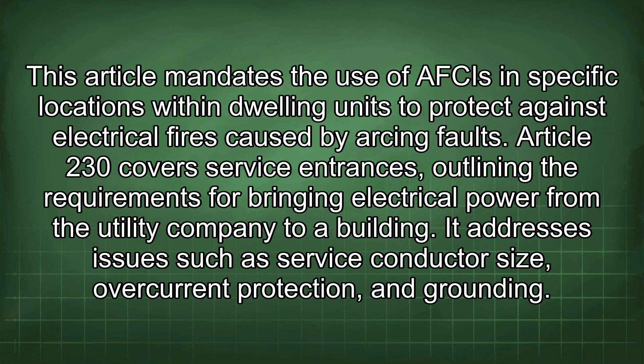Some specific examples of NEC articles and their relevance are Article 210.12, which pertains to arc fault circuit interrupter, or AFCI, protection. This article mandates the use of AFCIs in specific locations within dwelling units to protect against electrical fires caused by arcing faults. Article 230 covers service entrances, outlining the requirements for bringing electrical power from the utility company to a building. It addresses issues such as service conductor size, overcurrent protection, and grounding.